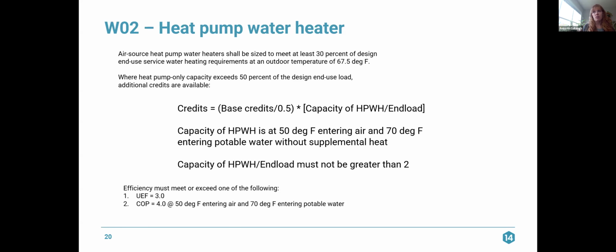So the capacity of the heat pump water heater is at a 50-degree entering air temperature and a 70-degree entering potable water temperature without supplemental heat. So it's just the capacity of that heat pump. If your capacity of your heat pump water heater divided by the end load is greater than 2, you can only use 2. The efficiency of your heat pump water heater must meet one of the following: a UEF of 3 or a COP of a minimum of 4 at 50 degrees entering air and 70-degree entering potable water temperature. So requirements around the efficiency of those heat pump water heaters, and then additional credits available for serving more of the building, total building load.